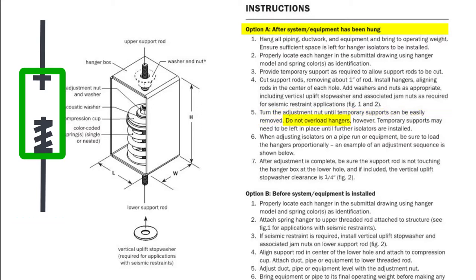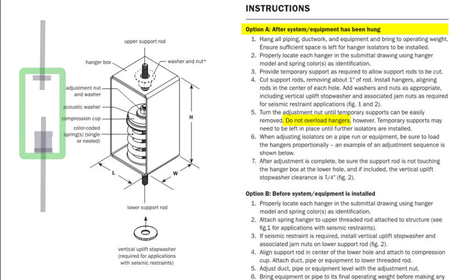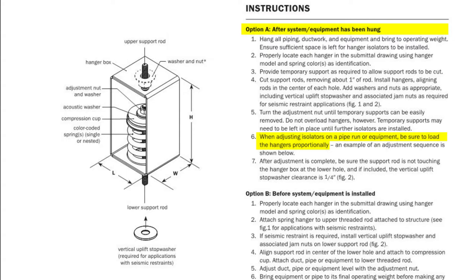It is important not to overload the springs, we don't want them to go flat, so the temporary supports may need to stay in place until additional isolators are added and then the system or equipment lifted all at once, loading the hangers proportionally. On equipment that usually means following a pattern such as is shown below. This shows adjusting the isolators in opposite corners and then adjusting the middle isolators.